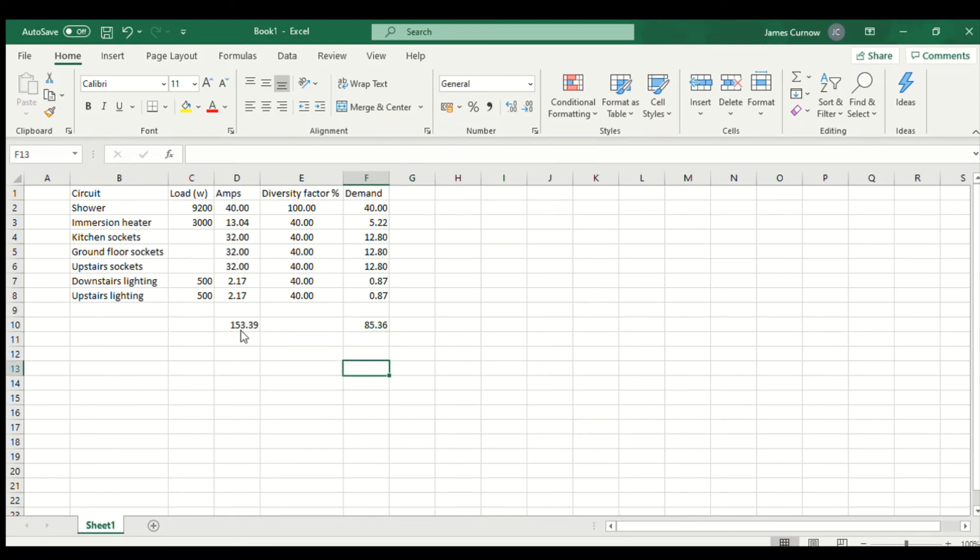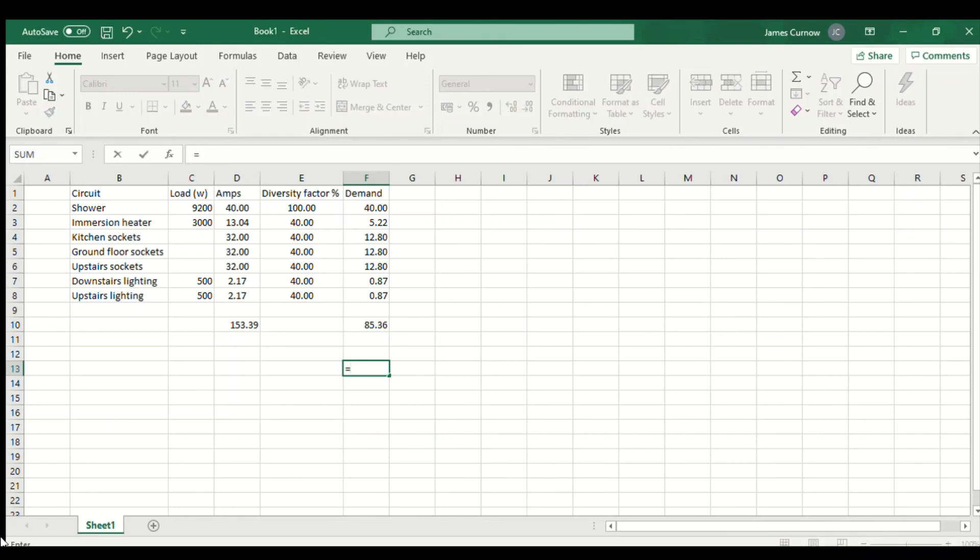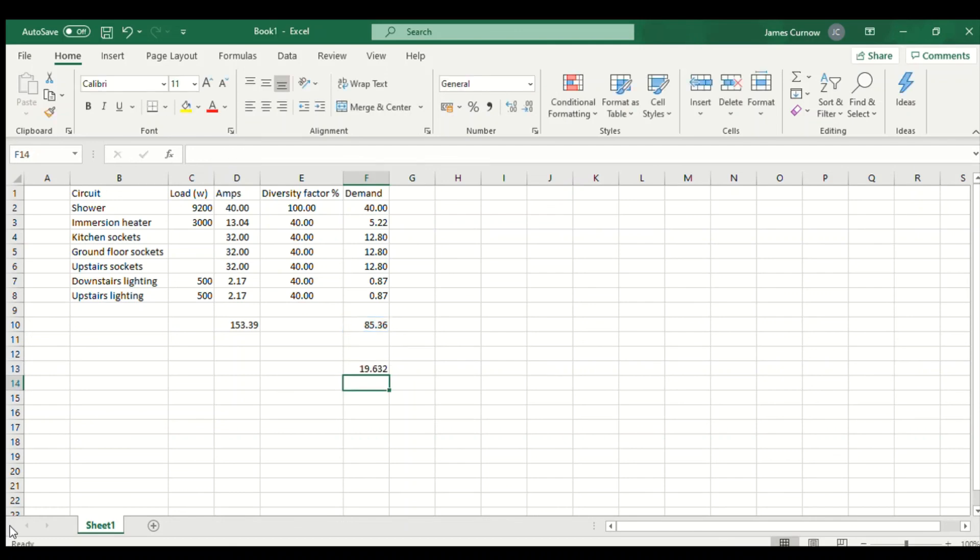The next thing I want to do is work out the maximum demand in kVA, which is very important if you want to apply for a new electricity connection, because the electricity supplier will ask for the demand in kVA. To do that you multiply the current by the voltage and then divide by a thousand. Click on the cell where you want the answer, type equals, then click on the current, asterisk for multiply, 230 volts, and then forward slash for divide, 1000. That gives me the answer of 19.63 kVA.